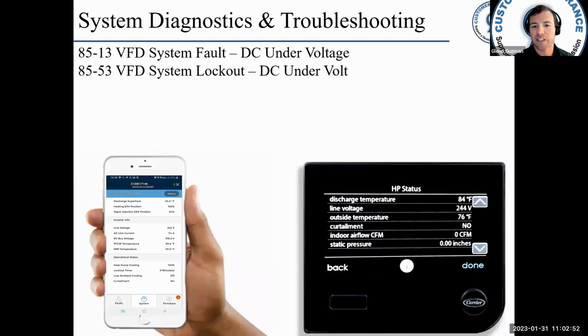8513 VFD system fault, DC under voltage, and 8553 DC undervolt lockout. Troubleshooting both faults is the same procedure. Verify high AC voltage on the UI and on the app and confirm it's within specs. Okay, so I'm looking at my line voltage, 244. I look on the app, line voltage, 244. Okay, I should be pretty close. You know, measure it with your meter.